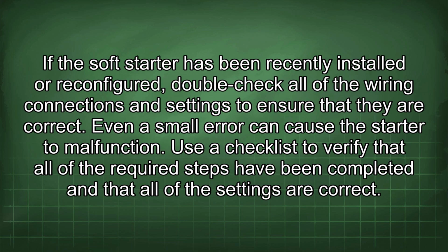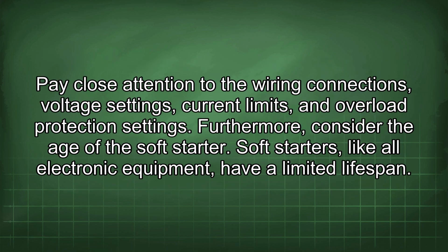If the soft starter has been recently installed or reconfigured, double-check all of the wiring connections and settings to ensure that they are correct. Even a small error can cause the starter to malfunction. Use a checklist to verify that all of the required steps have been completed and that all of the settings are correct. Pay close attention to the wiring connections, voltage settings, current limits, and overload protection settings.